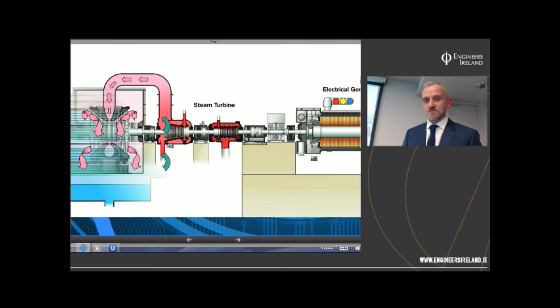Just one point of note there: when the gas turbine is started up, you do not have steam quality sufficient to put into the steam turbine, so you have to operate in bypass mode until the steam quality reaches the required levels. So there's a clutch here which is disengaged for a bypass operation, so that you can generate electricity with your gas turbine and your steam turbines in bypass. Once you get your steam quality correct, you can engage your clutch, you send the steam into the steam turbine, and you're getting power from both directions.